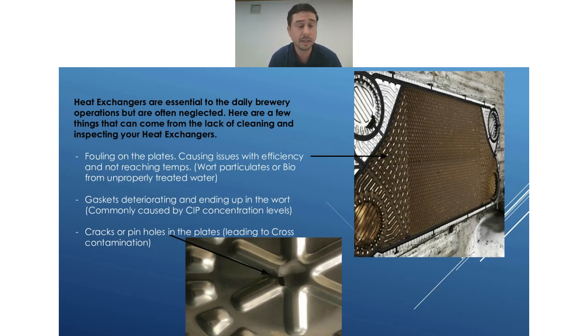So one good sign is if you're seeing the efficiency of the heat exchanger starting to drop, that may be one of the issues. It's a good thing to open up and inspect that and make sure nothing's going on there. Also, untreated water not being treated properly can cause some bio buildup—another reason to open these up.